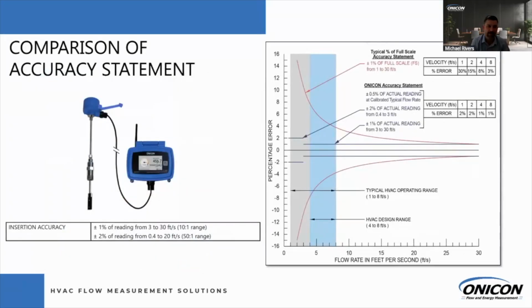All right, so I'd like to take a few minutes to talk about accuracy. This is one of the most important slides in here because it demonstrates the difference between a 1% of reading device versus a 1% of full scale device. And I talk to engineers all the time: 1%, they must be the same. What's the difference? That red line on the graph is a 1% of full scale device. The blue line is the accuracy of our FT-3500. Both meters at 30 feet per second can read 1%. But when you start looking at the applications these meters are living in, that blue shaded region is typical chilled water, hot water, condenser water applications at 4 to 8 feet per second.